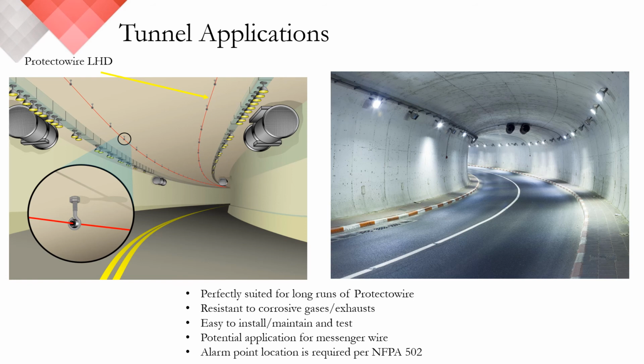Picture, if you will, being able to, in real time, tie the data into your HVAC and CCTV systems. As ambient conditions begin to rise due to increased traffic, the HVAC system can automatically kick on to open vents and increase circulation. In the case of a fire, the CCTV cameras are programmed to pick up the event, providing operators in the control room the ability to see what type of event is occurring.